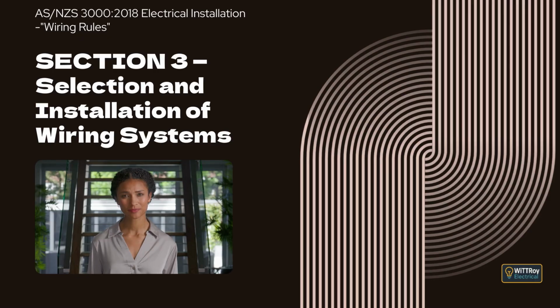Clause 3.11.4.4, Minimum depth of cover. This clause explains that underground wiring systems must be installed with not less than the minimum depth of cover specified for the category of system in the location. The depth is measured vertically from the surface of the ground or from the surface of any concrete placed above the wiring system, and the required depth varies depending on whether the wiring is within or outside a building and whether additional protection is provided.